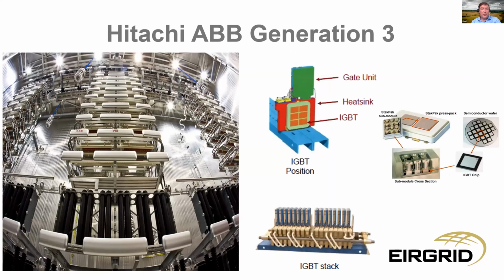This is a Generation 3 VSC converter from Hitachi ABB Power Grids. It consists of series connected IGBTs that require full pulse width modulation. This results in higher switching losses and harmonic challenges. To break it down, the picture shows the inside of the valve hall where switching operations occur. There are 3 valves, VA, VB, VC, which are replicated in each of the converter stations. The valves are suspended from the ceiling and are made up of 32 IGBT stacks.